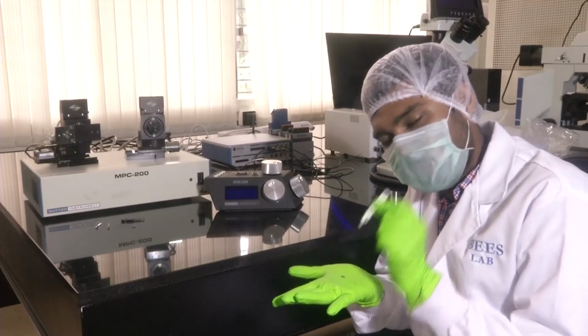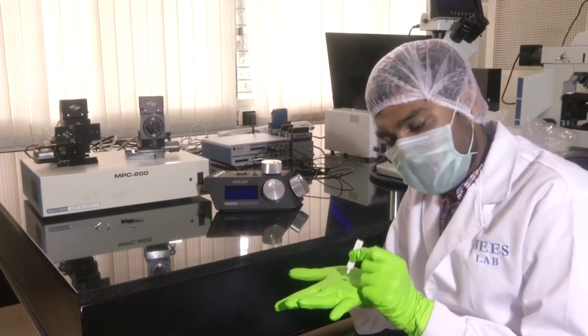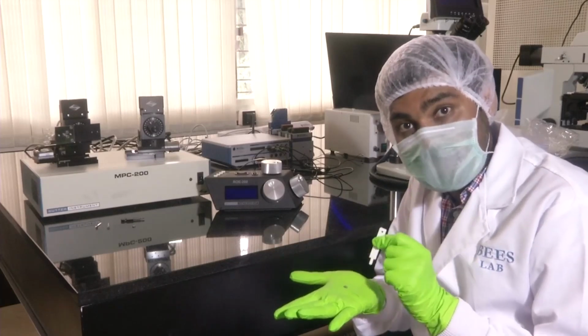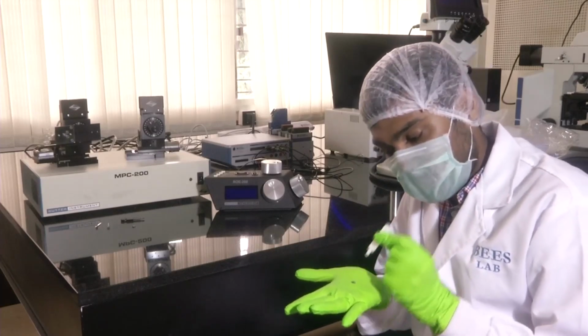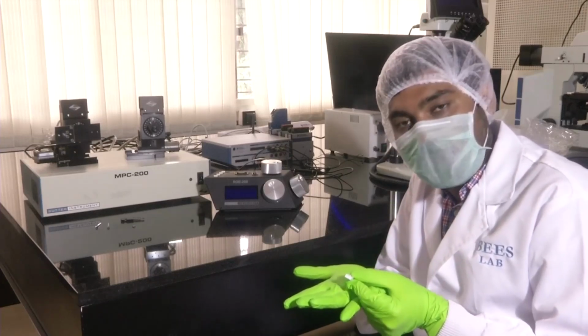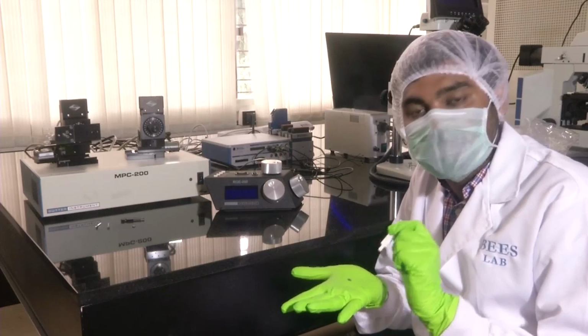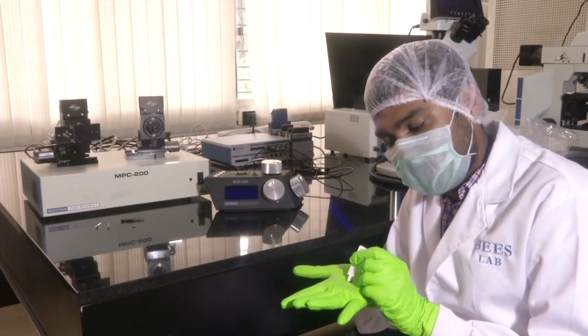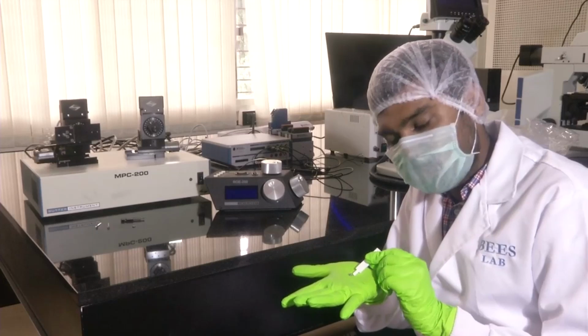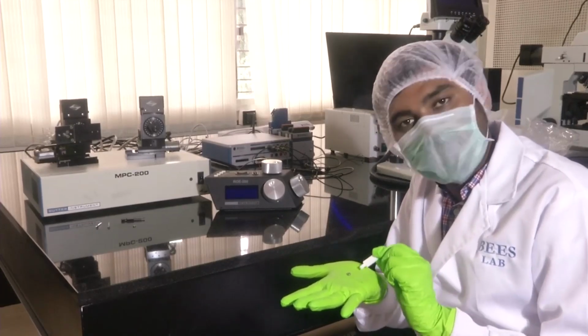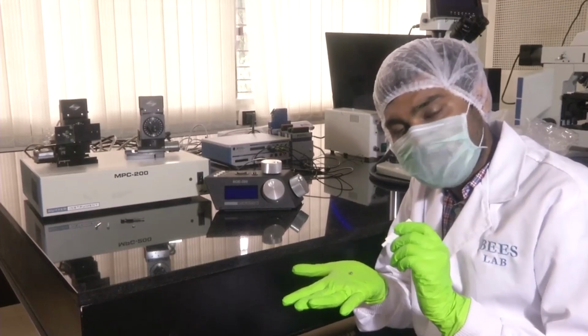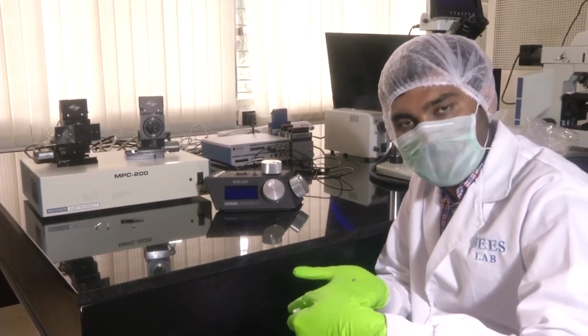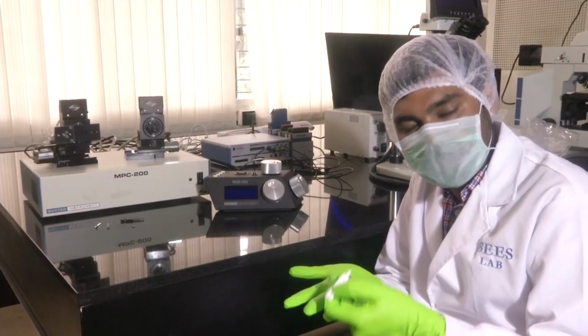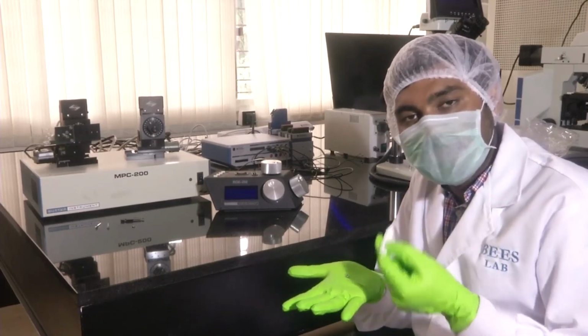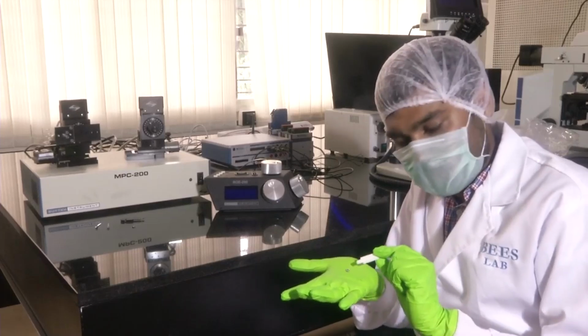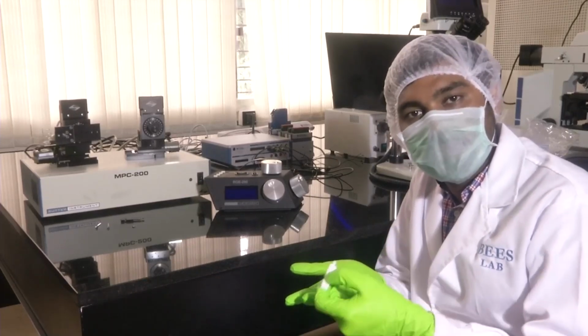When we press, this indenter will apply a force on the tissue. The tissue, because of its elasticity and stiffness properties, will translate a different pressure at the bottom of the tissue, on the surface of the pressure sensor. So, we press it, and then this tissue, because of its elasticity, translates a different pressure on the surface of the sensor. This way, whatever information gets measured from these contact points as the pressure being measured will inherently have the information of the stiffness of the tissue in the measured value.